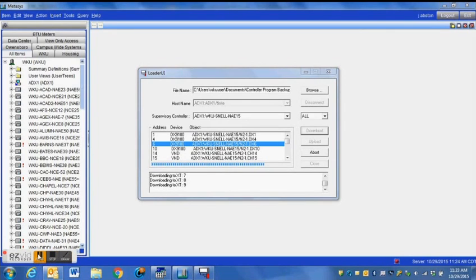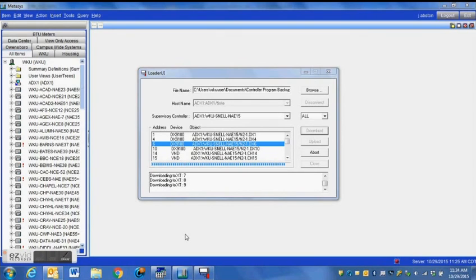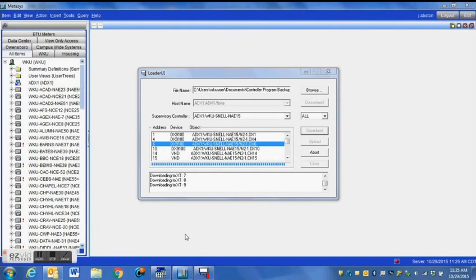Now looking in Metasys, if you were to go back to that window, you would actually see points offline under your system, and that is because the extension modules are being loaded. Now don't worry about that, they should come back in once the program gets downloaded to them.